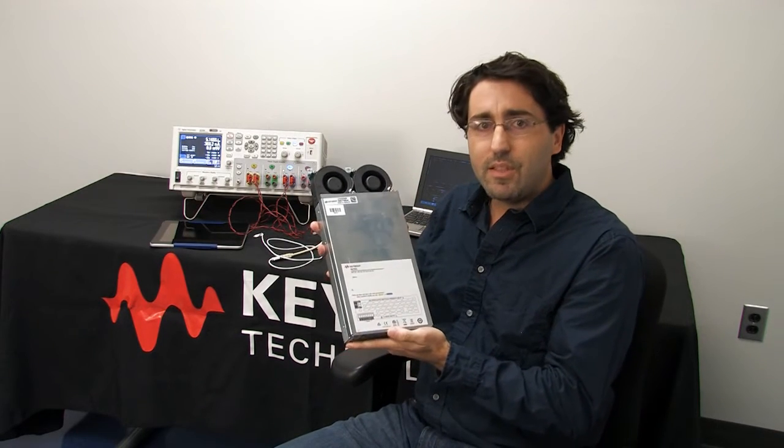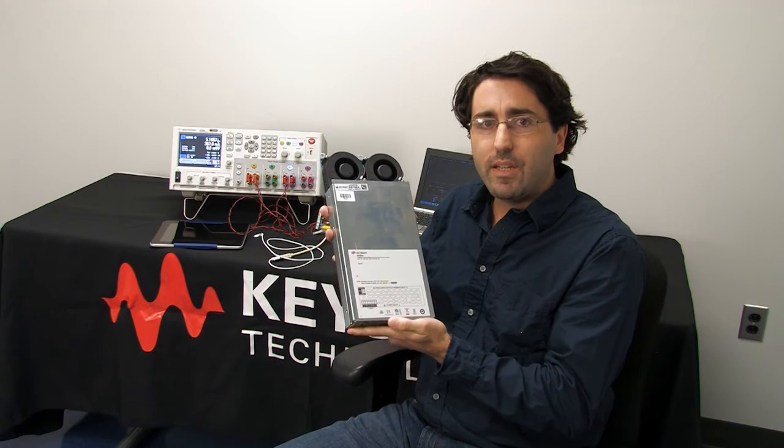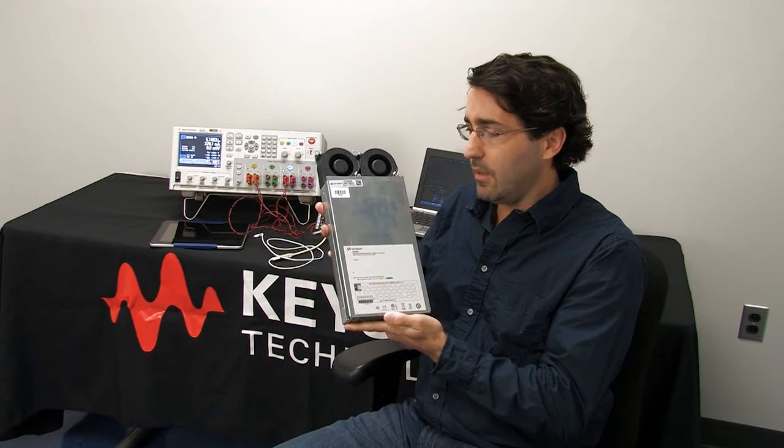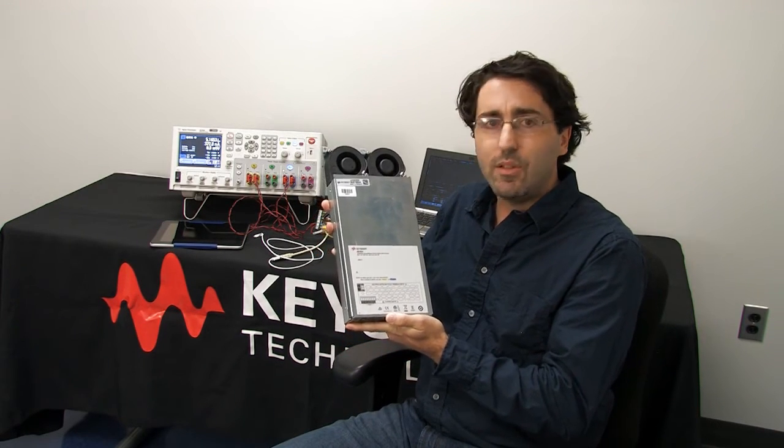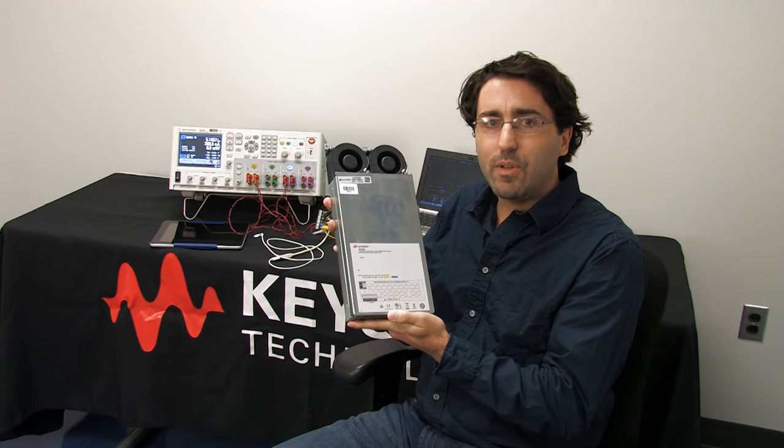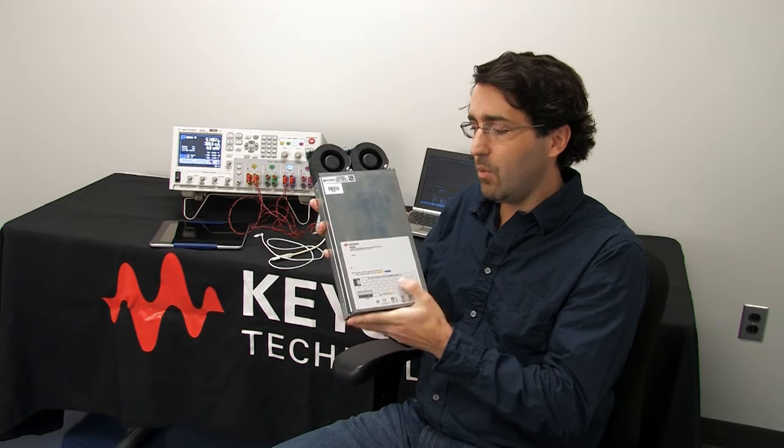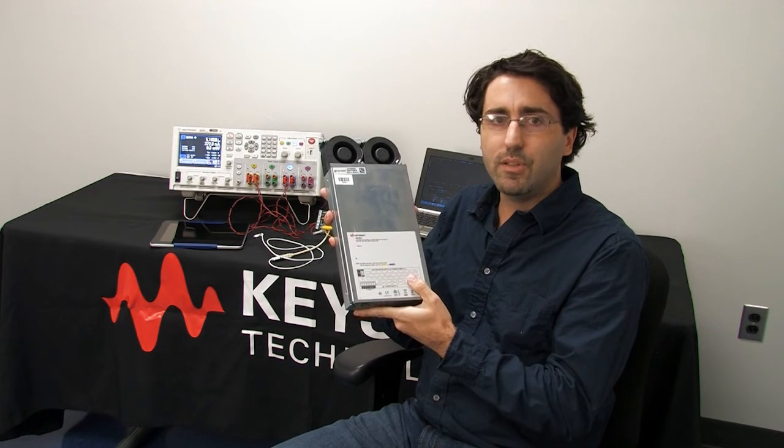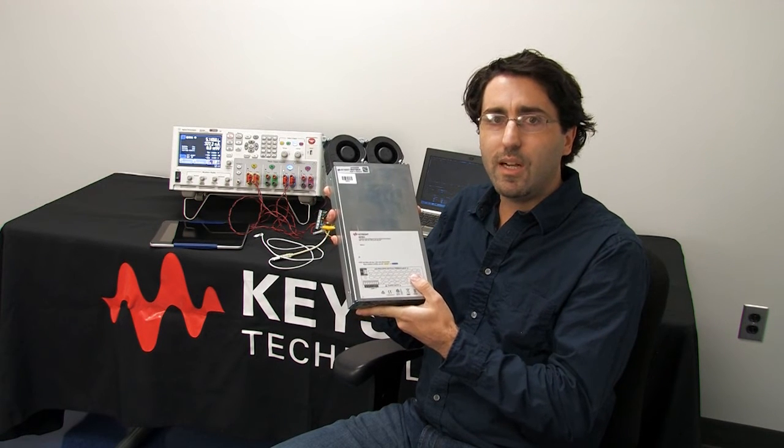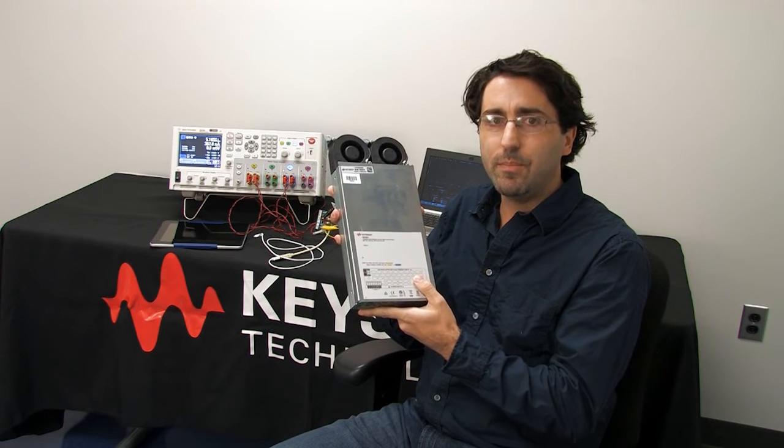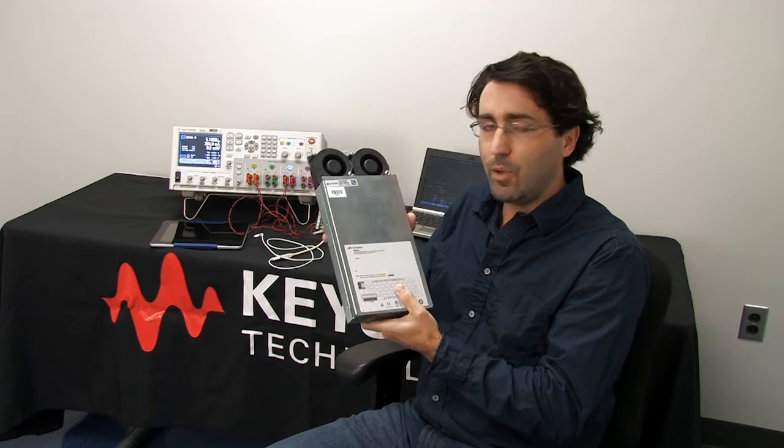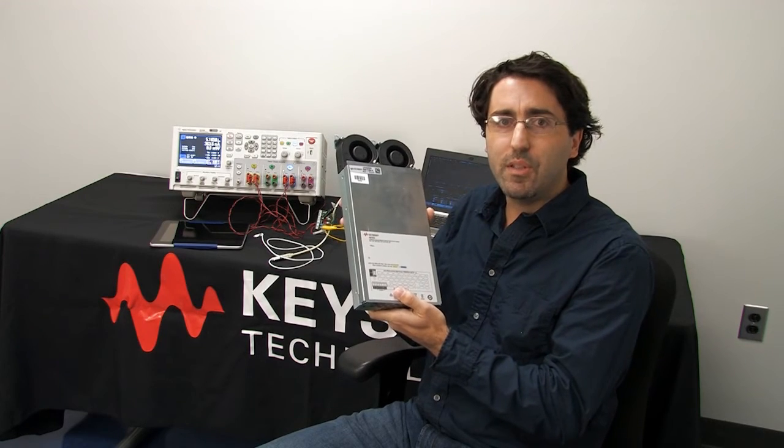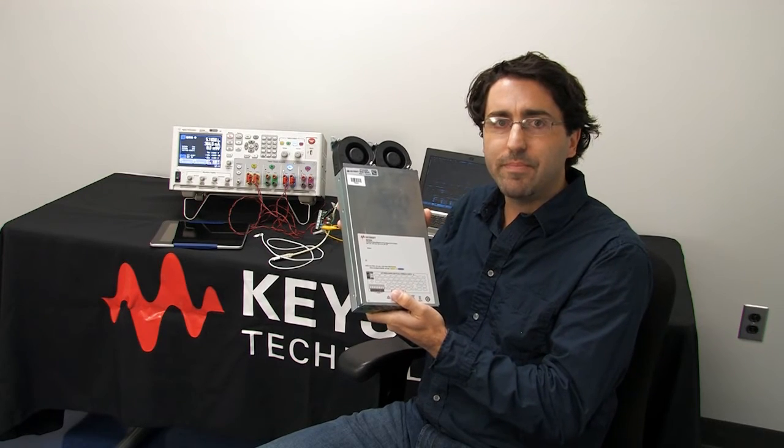Here's the new N6785A SMU. You can notice it's a double-wide module as opposed to single-wide, so it actually does take two slots in the mainframe. I'm going to go ahead and install this in the mainframe now.